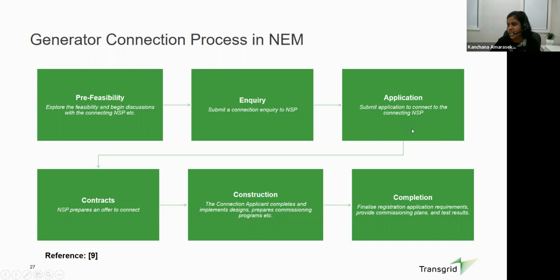So we were in the connection application stage. As I mentioned, once they submit the connection application, which includes the GPS document and the intensive GPS compliance assessment highlighting that they can meet those technical requirements, usually AEMO and NSPs will review those, and once they are happy, the connecting party gets what is called the offer to connect. The FIA, the full impact assessment, is also part of this application stage, which I mentioned during my explanation on system strength. So after the connection application, they get the offer to connect. And then after the offer to connect, they can start constructing their plant and prepare for commissioning. And before they commission, they have to achieve generator registration.